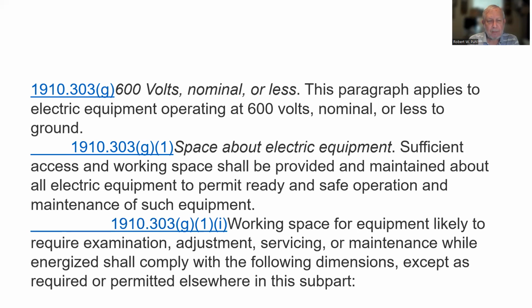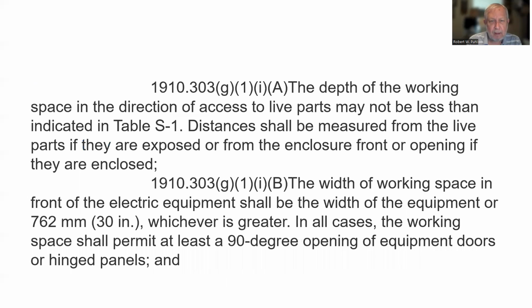Space about electrical equipment. Sufficient access and working space shall be provided and maintained about all electric equipment to permit ready and safe operation and maintenance of such equipment. Working space for equipment likely to require examination, adjustment, servicing, or maintenance while energized shall comply with the following dimensions, except as required or permitted elsewhere in this subpart. There we go. With more stuff like that. The depth of the working space in the direction of access to live parts may not be less than indicated in table S1. Distances shall be measured from the live parts if they are exposed or from the enclosure front or opening if they are enclosed.